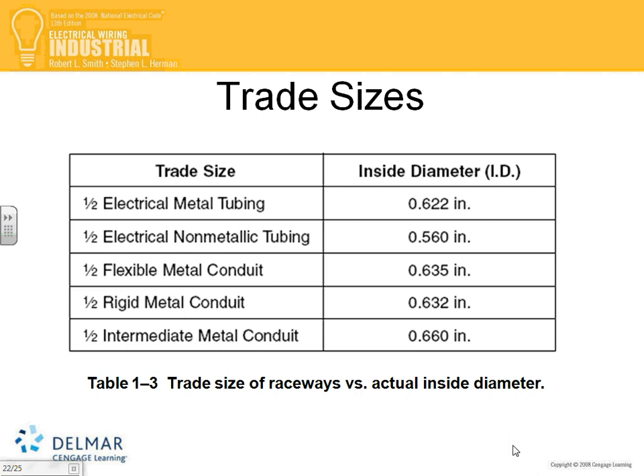Trade sizes, I want to bring to your attention always, we touched on that one last quarter, guys, too. If you go to a 1/2 inch, look at these. All these are 1/2 inch, but look at the actual interior diameter of them. They're all different. So what is 1/2 inch EMT? It's a trade name. It's not an actual size. That will allow you, when you're looking at how many conduits you can fit, to see that 1/2 inch EMT is different than PVC. That's because it's just a trade name.